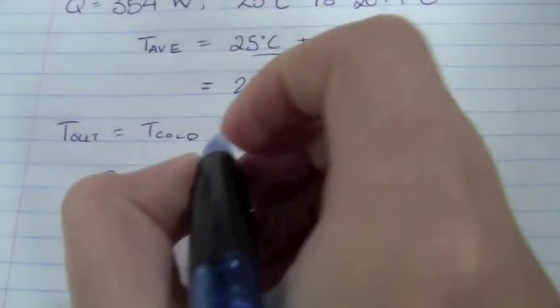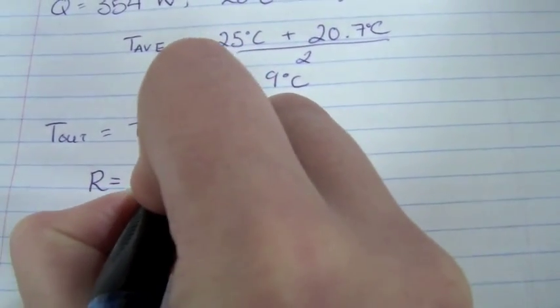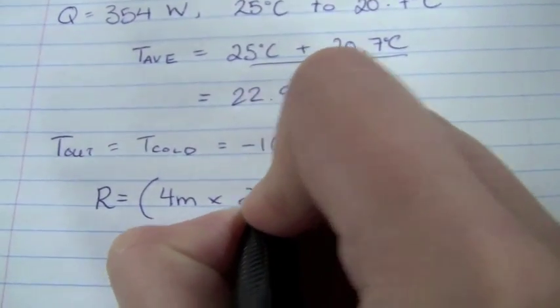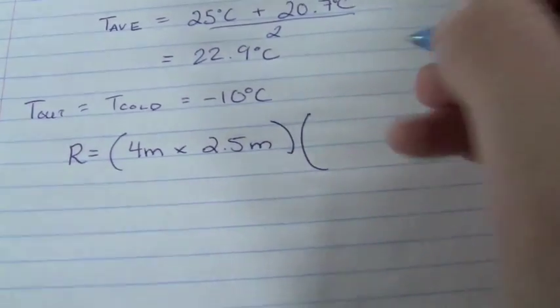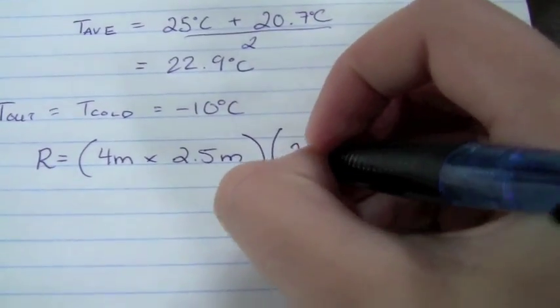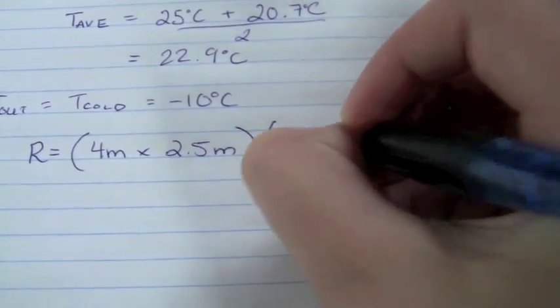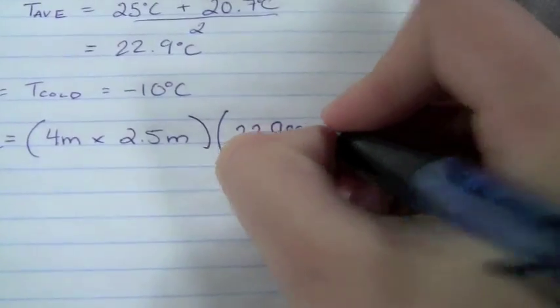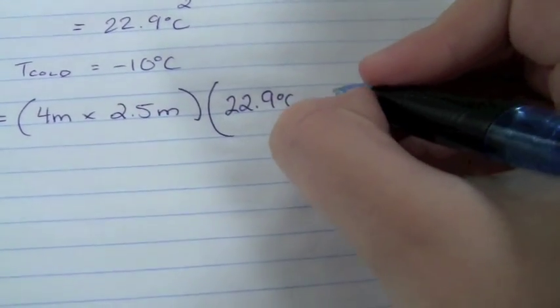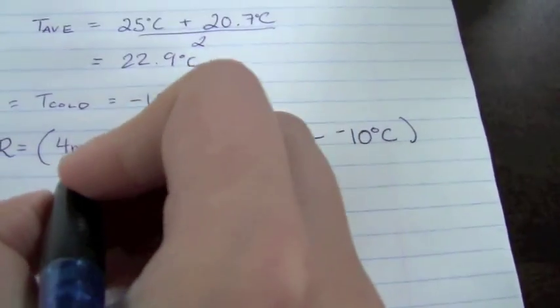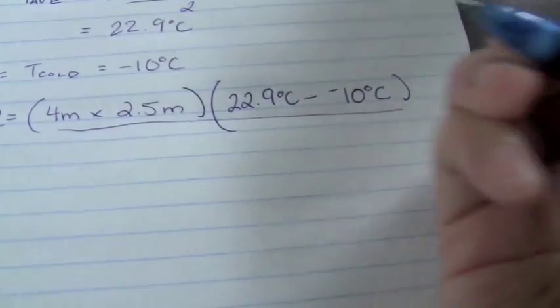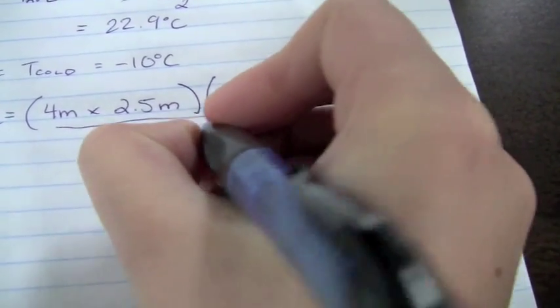Using the same room that we had previously, so one with an area of 4 meters times 2.5 meters, we can plug in our numbers. So our T-hot is 22.9 degrees Celsius, and we need to subtract our T-cold from that, so minus, minus 10 degrees Celsius. All divided by our heat loss, which is 354 watts.